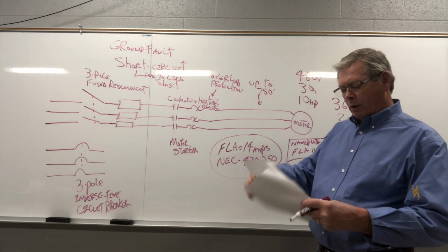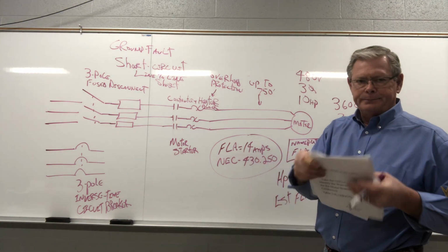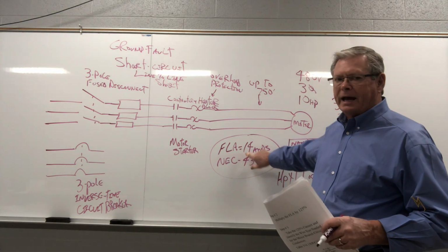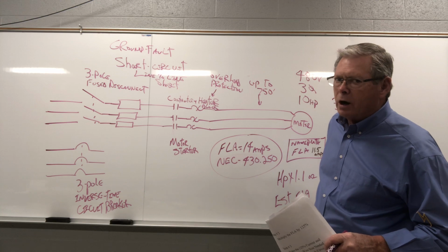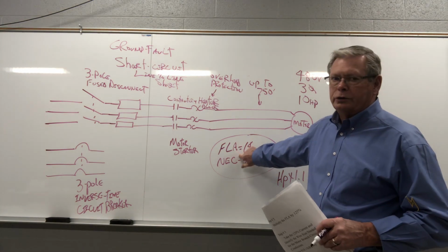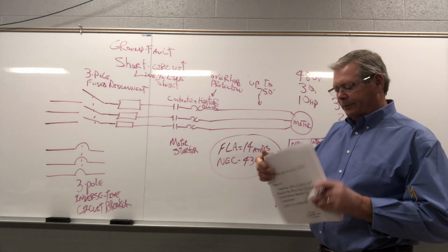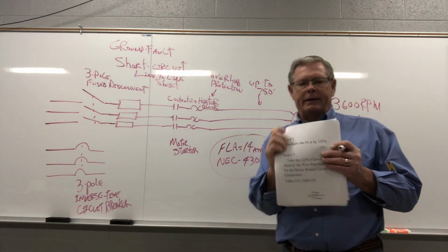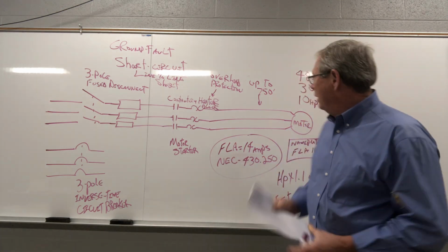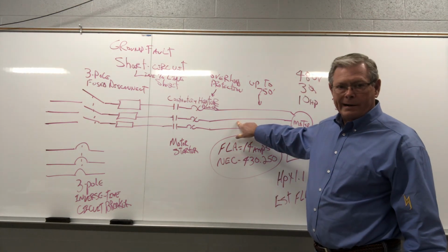Okay, so now what we do, we go to step 2. We found 14 amps off the table. Don't use nameplate. It's wrong to use nameplate. You use the table current, 14 amps. Here it says multiply the full load current by 125%. Now, why do we do that? We are getting ready to select wire.